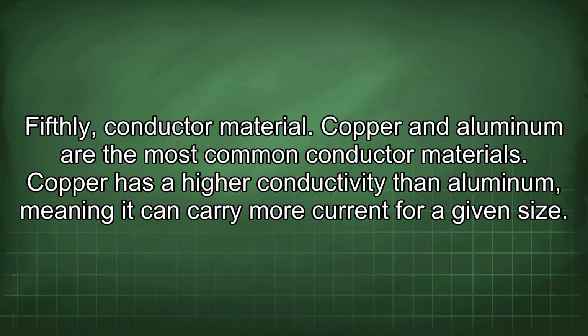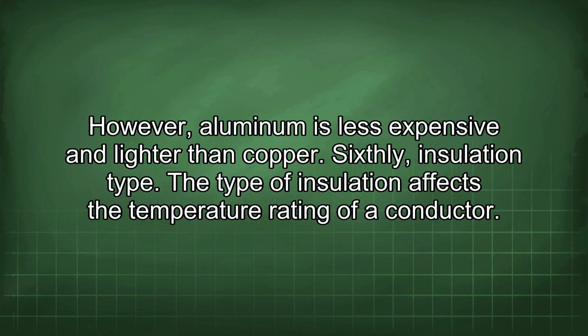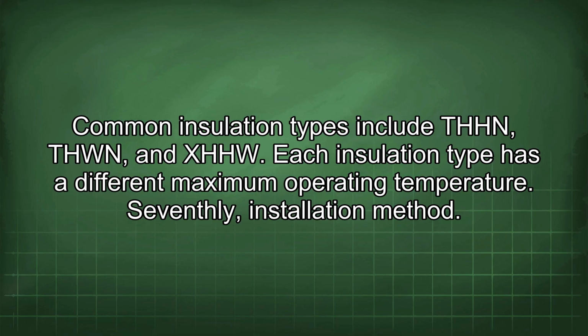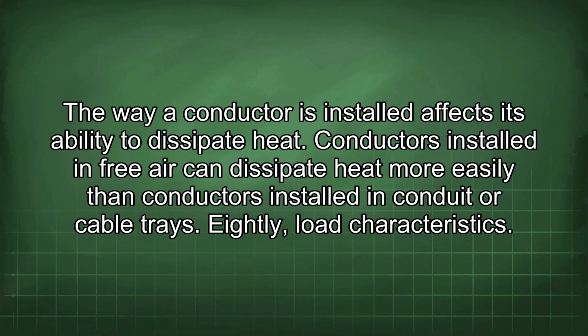Fifthly, conductor material. Copper and aluminum are the most common conductor materials. Copper has a higher conductivity than aluminum, meaning it can carry more current for a given size. However, aluminum is less expensive and lighter than copper. Sixthly, insulation type. The type of insulation affects the temperature rating of a conductor. Common insulation types include THHN, THWN, and XHHW. Each insulation type has a different maximum operating temperature. Seventhly, installation method. The way a conductor is installed affects its ability to dissipate heat. Conductors installed in free air can dissipate heat more easily than conductors installed in conduit or cable trays.